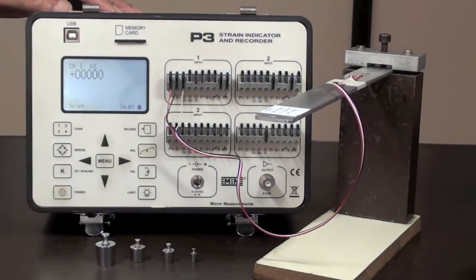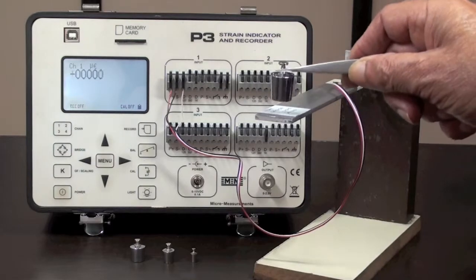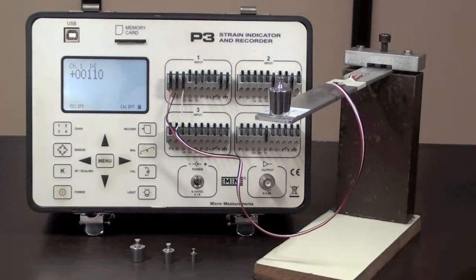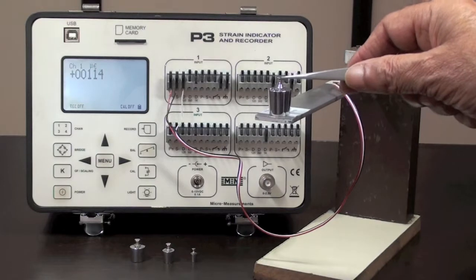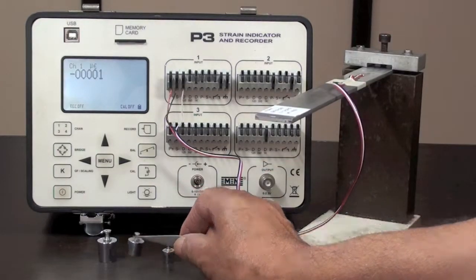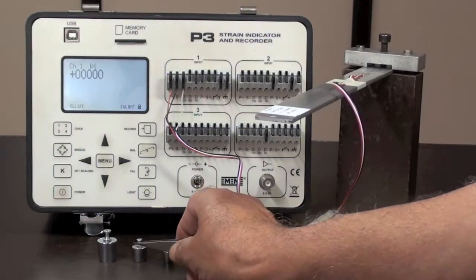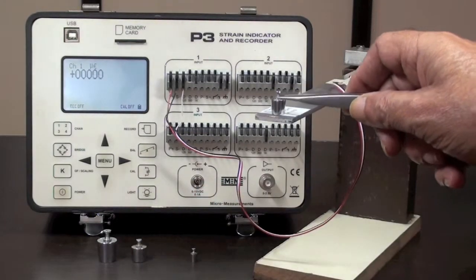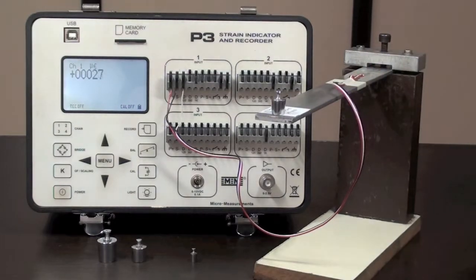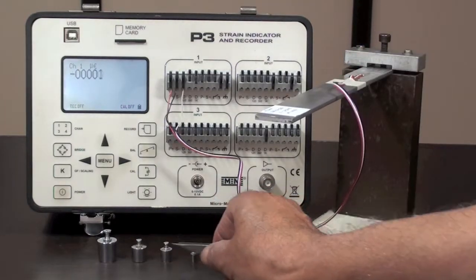Now the last digit on the display will correspond to 0.1 microstrain. With 20 grams on the beam, the reading should be 11.1 microstrain. With 10 grams, it should be 5.5 microstrain. With 5 grams, it should be 2.7 microstrain and with 1 gram, the reading should be 0.5 microstrain.